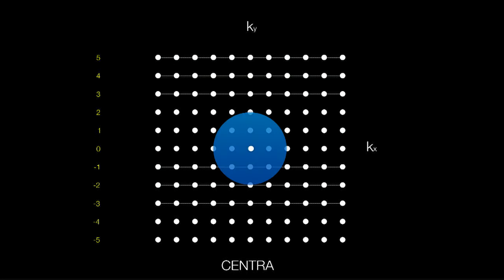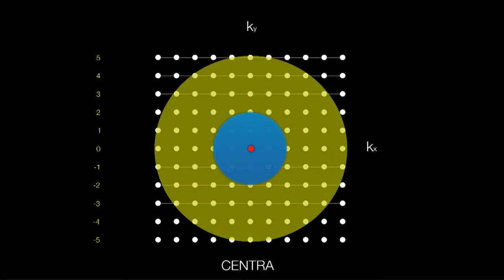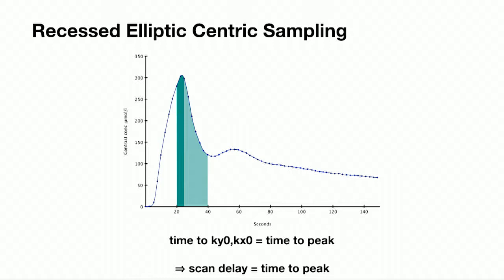Centra is a Philips recessed K-space approach with a pseudo-random acquisition around the centre for the first four seconds or so, acquiring the very centre of K-space when we're in a plateau phase of contrast enhancement, then moving on to the edges of K-space with a K-space shutter at the periphery. In an elliptical centric recessed example, the peak falls in the plateau area. Using these techniques we can do contrast-enhanced MRA all the way down, getting very high spatial resolution at small vessels without too much venous contamination.